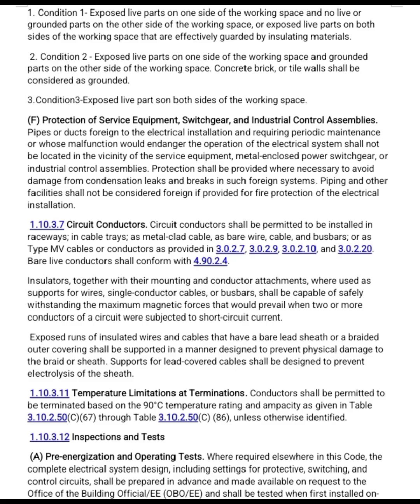Letter F. Protection of service equipment, switchgear, and industrial control assemblies. Pipes or ducts foreign to the electrical installation and requiring periodic maintenance, or whose malfunction would endanger the operation of the electrical system, shall not be located in the vicinity of the service equipment, metal-enclosed power switchgear, or industrial control assemblies. Protection shall be provided where necessary to avoid damage from condensation, leaks, and breaks in such foreign systems. Piping and other facilities shall not be considered foreign if provided for protection of the electrical installation.